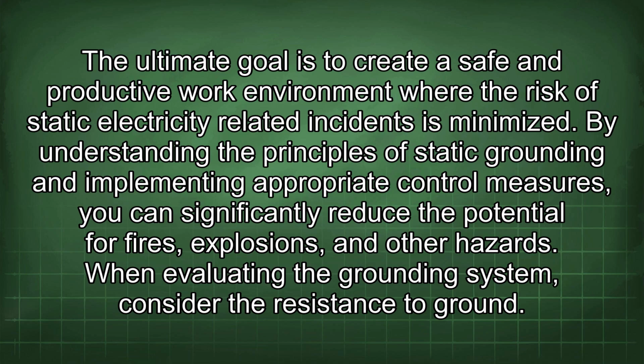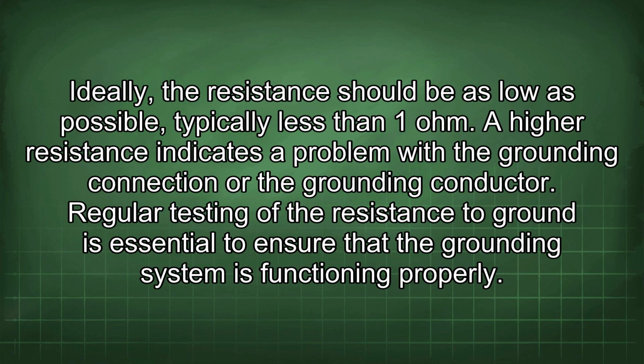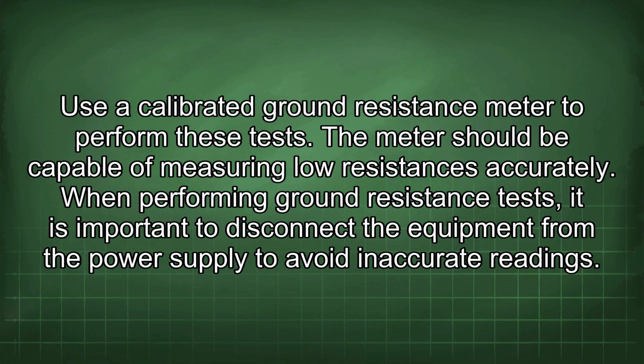When evaluating the grounding system, consider the resistance to ground. Ideally, the resistance should be as low as possible, typically less than 1 ohm. A higher resistance indicates a problem with the grounding connection or the grounding conductor. Regular testing of the resistance to ground is essential to ensure that the grounding system is functioning properly. Use a calibrated ground resistance meter to perform these tests. The meter should be capable of measuring low resistances accurately.